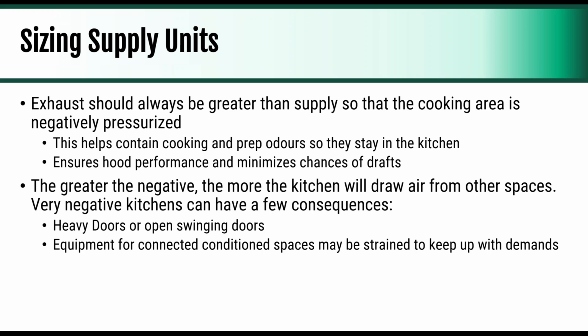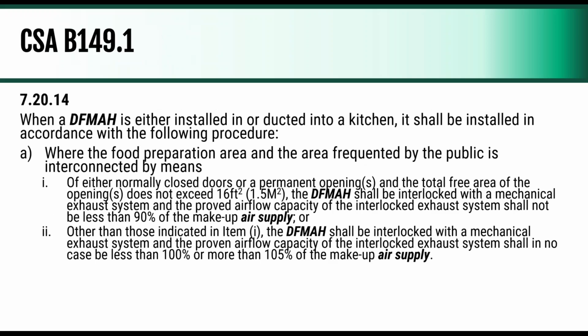So if you've got, call it a 35-degree day in Toronto, and your equipment for the dining area is sized for 30-degree days max, you're already going to be behind. But then if you've got a really negative kitchen, the exhaust is going to be pulling the conditioned air from the dining space, and you're going to have a really hard time keeping that to your target temperature. And so that's where we'll show you our typical guideline on supply sizing on the next page, but that's just one thing to keep in mind.